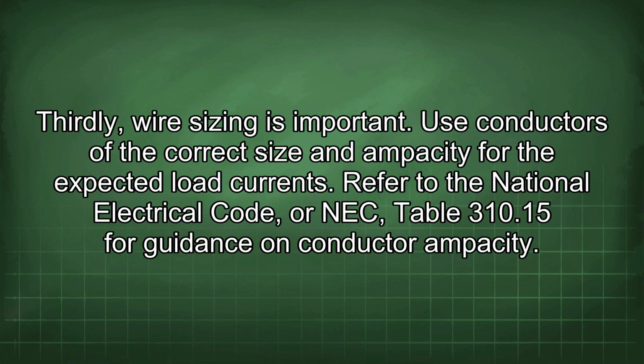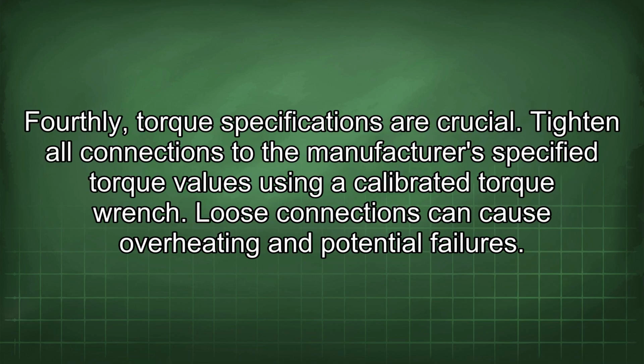Thirdly, wire sizing is important. Use conductors of the correct size and ampacity for the expected load currents. Refer to the National Electrical Code, or NEC, Table 310.15 for guidance on conductor ampacity. Fourthly, torque specifications are crucial. Tighten all connections to the manufacturer's specified torque values using a calibrated torque wrench. Loose connections can cause overheating and potential failures.